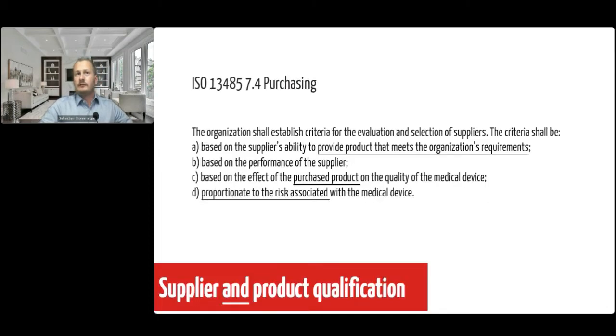If we look into ISO 13485, Chapter 7.4 Purchasing, we see what the organization needs to do to evaluate and select the suppliers. And the criteria shall be based on the supplier's ability to provide products that meet the organization's requirements. So first of all, the organization's requirements need to be specified, which is very often not the case. And it needs to be based on the performance of the supplier. But then you look at C and D, based on the effect of the purchased product. So therefore, you need to estimate what the risks associated with the product are. And this is outlined in point D, proportionate to the risk associated with the medical device.